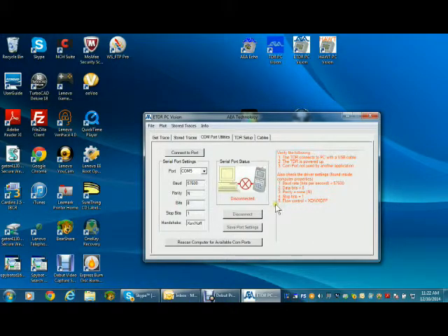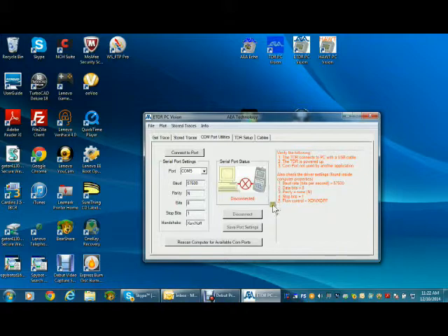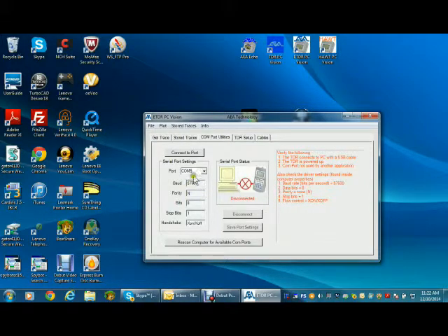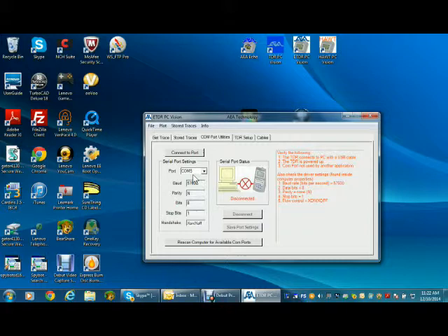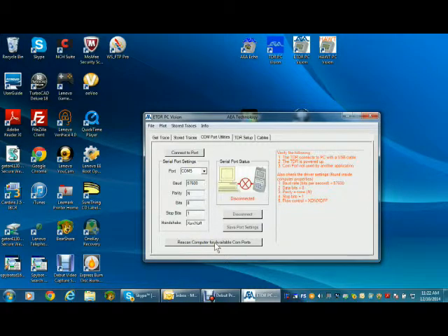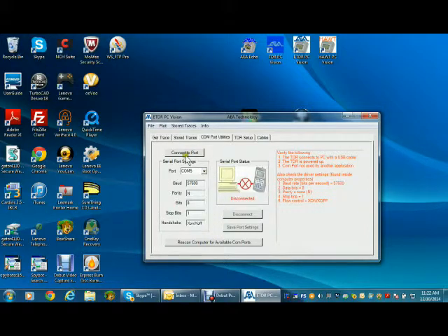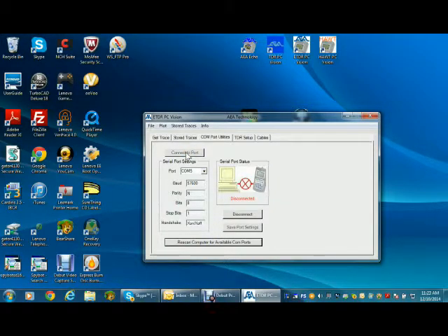Next, look to see if a COM port has been designated. If not, press rescan to find an available port, which will appear at the top of the serial port settings box. Next, press connect to port to complete the connection and note the serial port status box change. Now eTDR PC Vision can communicate with the TDR.